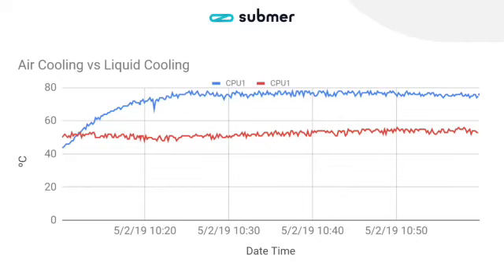A lot of people think that with immersion cooling, your processors and GPUs will run hotter than in air because we talk about a higher set point. However, this is not the case. We see that the temperatures reached in air under 100% load are up in the high, let's say mid 70s, all in Celsius. And here we're seeing anywhere from 49 to 52, 53 degrees in the liquid.